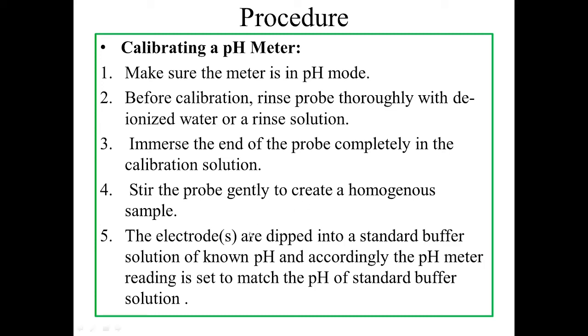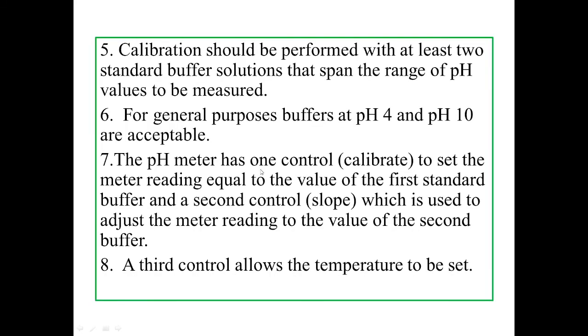So the electrode, after cleaning, is first dipped completely into the calibration solution, that is, the standard buffer solution having known pH. Stir it gently. Adjust the pH meter reading so as to match the pH of the standard buffer solution. And calibration, as I said, has to be performed using at least two buffers. For general purposes, pH 4 and pH 9.6 or pH 10 are taken.